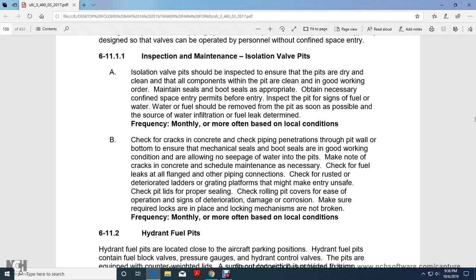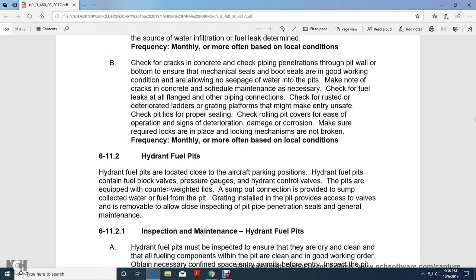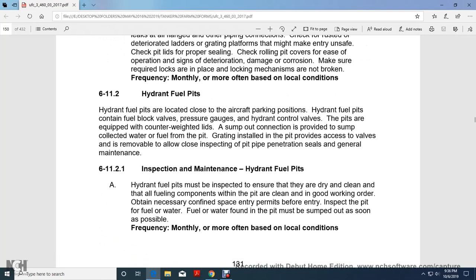Check pit lids for proper sealing. Check the rolling pit cover for ease of operation and signs of deterioration, damage, or corrosion. Make sure required locks are in place. Locking mechanisms should not be broken. Inspect monthly or more often based on local conditions. Hydrant fuel pits.